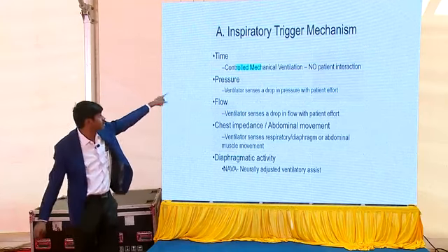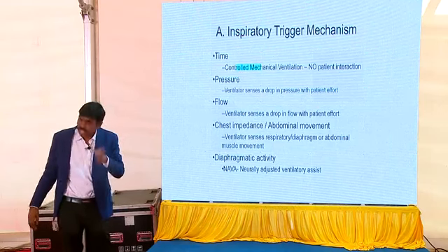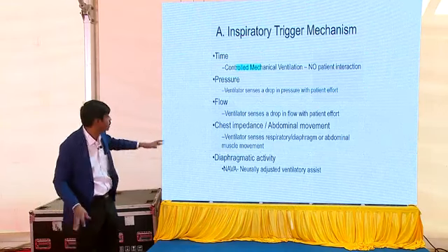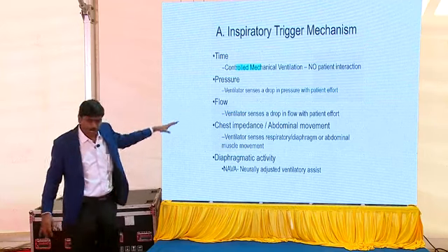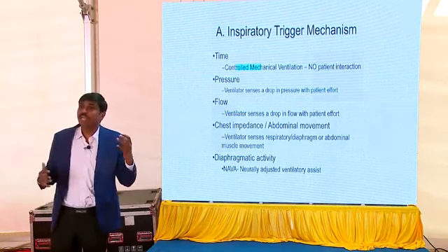That's called the CMV, NO patient interaction. We don't use this at all. There are some ventilators which still have a CMV mode of ventilation. Next comes the pressure trigger.